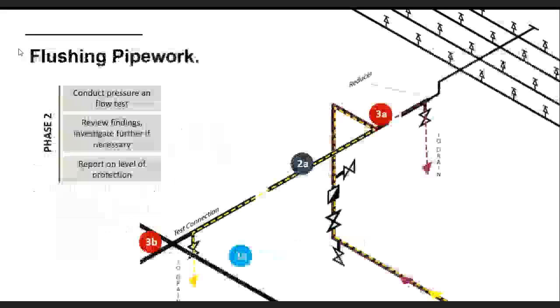Okay, moving on - let's have a few slides looking at flushing now. This diagram was actually created for a slightly different purpose, but I've put it in here anyway. It shows the water from the water supply coming up through the alarm valve and then opening the drains, which should be located there. These drains at the end of the distribution are called for as part of the codes.